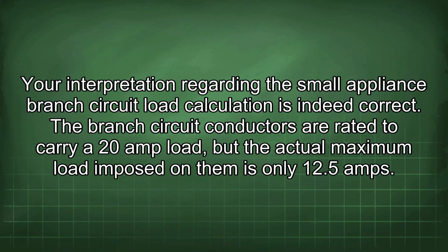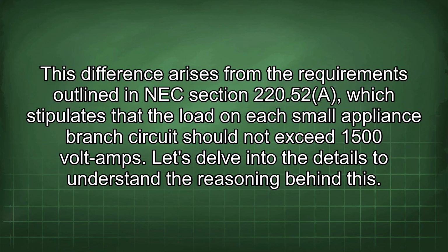Your interpretation regarding the small appliance branch circuit load calculation is indeed correct. The branch circuit conductors are rated to carry a 20 amp load, but the actual maximum load imposed on them is only 12.5 amps. This difference arises from the requirements outlined in NEC section 220.52(A), which stipulates that the load on each small appliance branch circuit should not exceed 1500 volt amps. Let's delve into the details to understand the reasoning behind this.